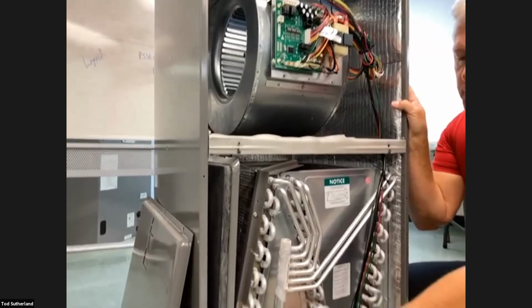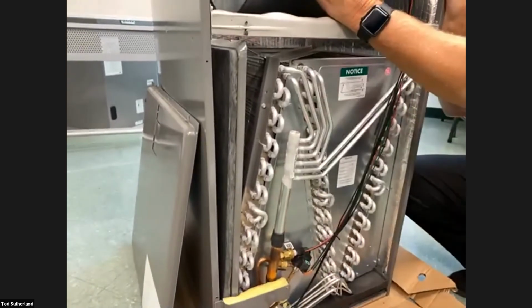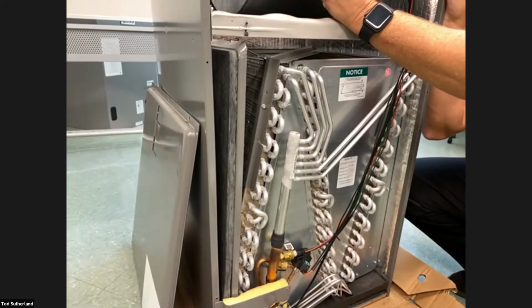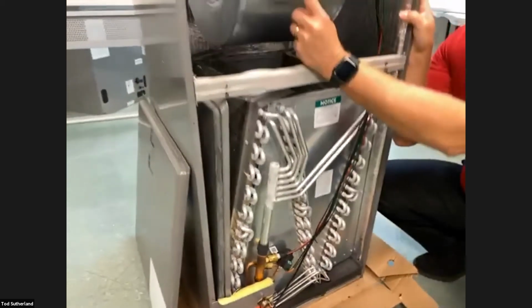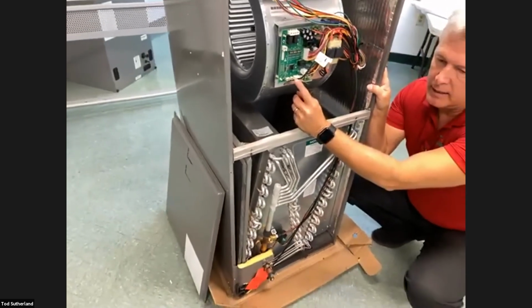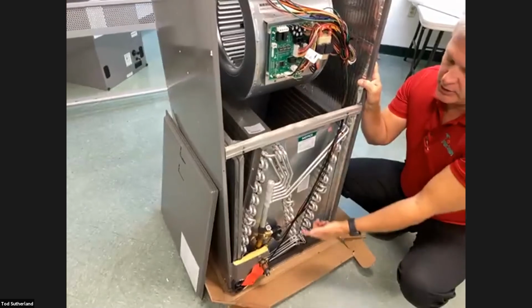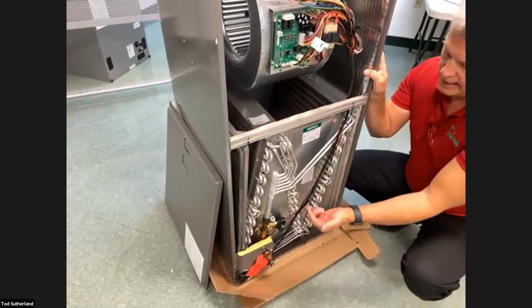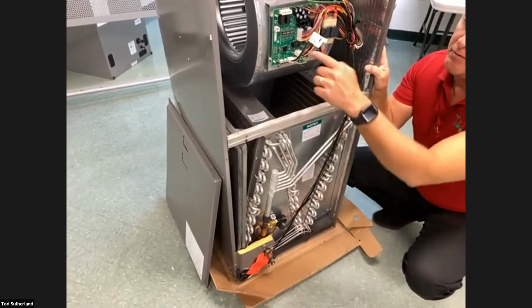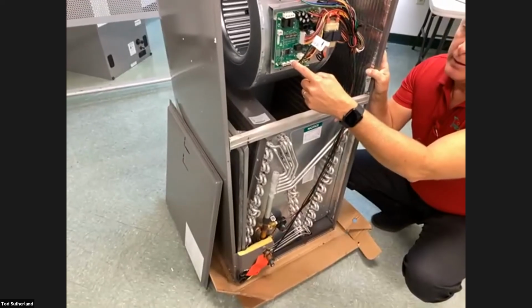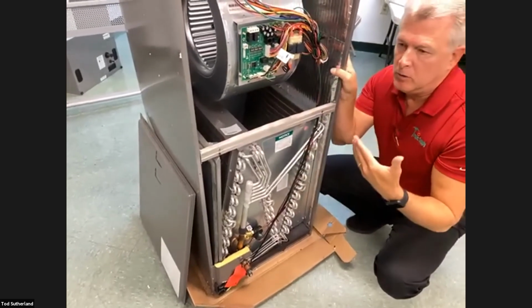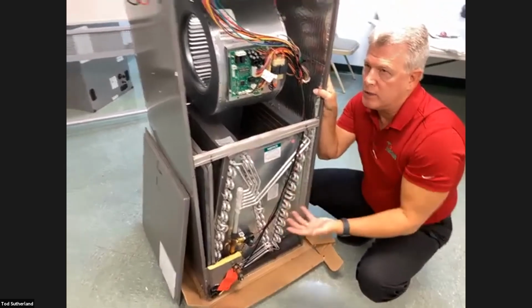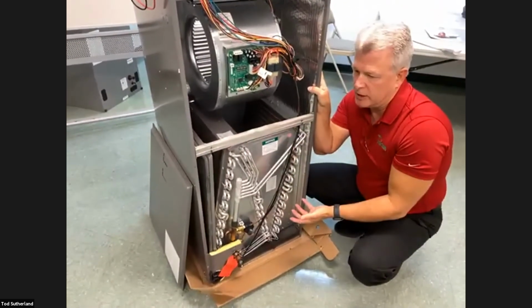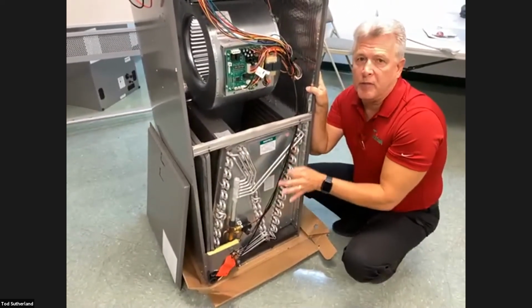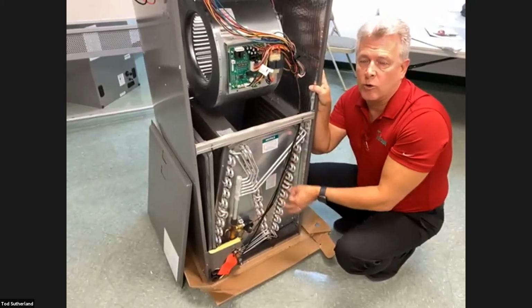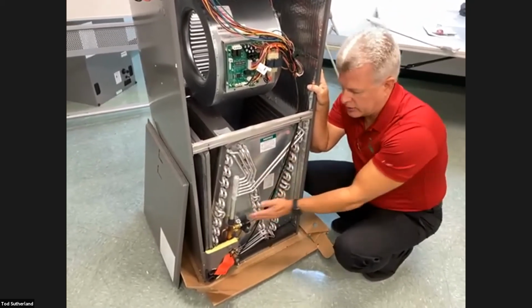And then from the pressure transducer back to the board, between the black and green wire, you should be getting between 0.5 and 4.5 volts. So 5 volts to the pressure transducer, and then 0.5 to 4.5 back to the board. Now, if you're getting that voltage, you know that the board is functioning properly, that your voltage is functioning properly, but we still don't know if those voltages are reading the correct pressure on the suction line.